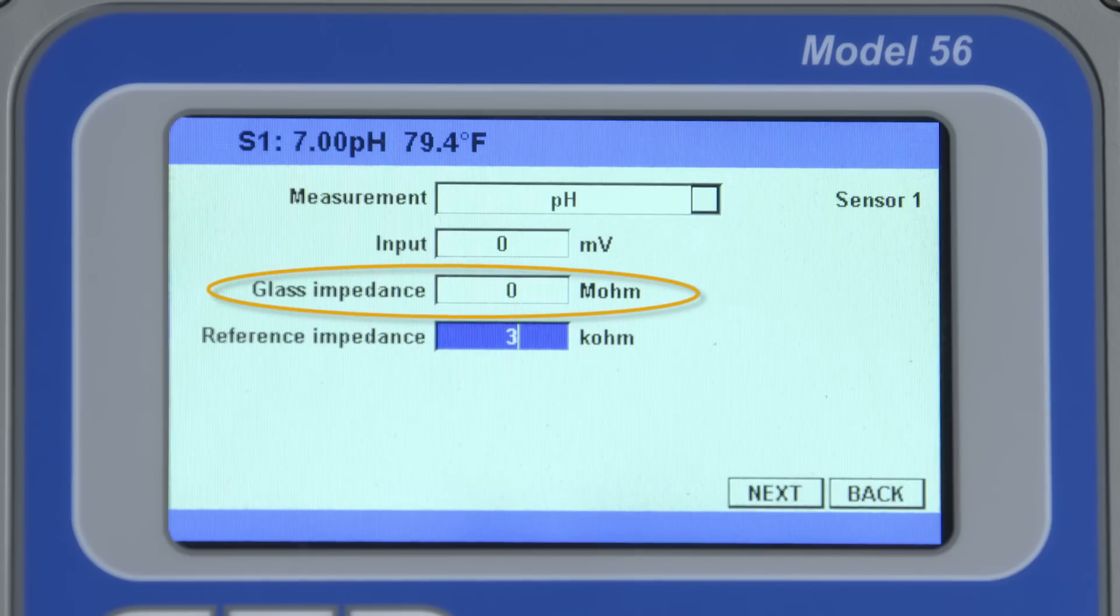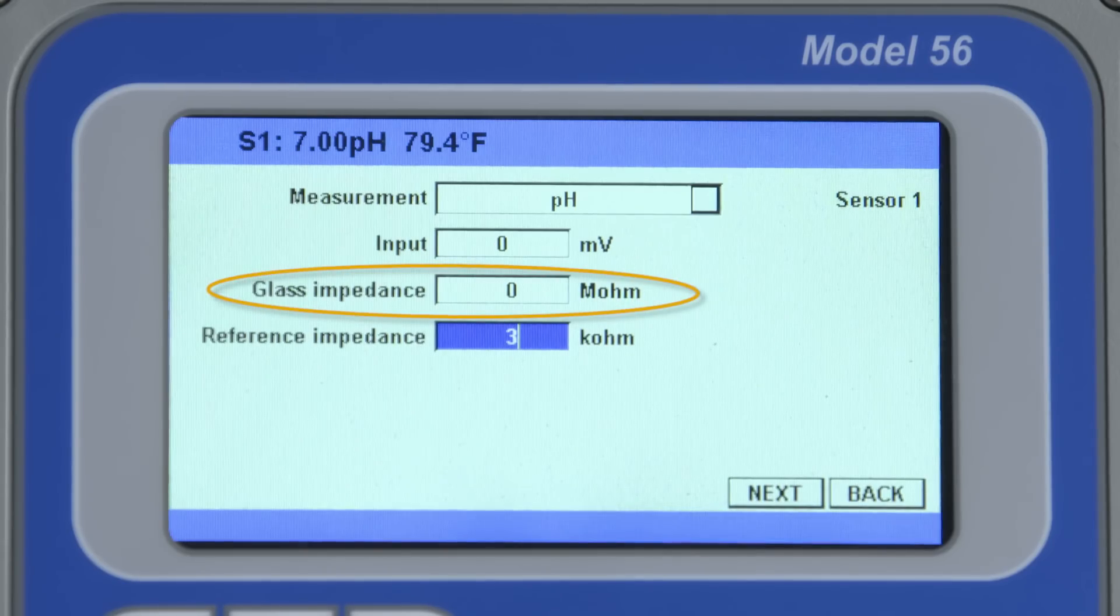That lets you know that the sensor either needs to be cleaned or resubmerged into the process fluid. A low, near zero glass impedance indicates that there is a crack in the glass bulb.